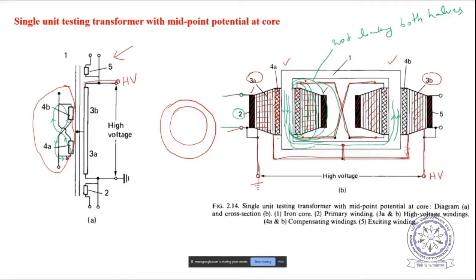How did the voltages become same? By establishing certain circulating current. This current will produce additional flux in such a way that it counters some of the excess leakage flux on one side and the deficit leakage flux on the other. For that it creates additional leakage flux, balancing the total flux so that the windings in the first leg and the second leg have exactly the same flux linking them.